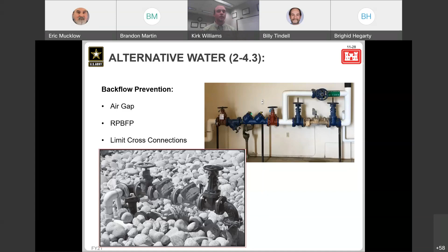This photo is from that AWWA manual, showing where you have a potable source and a non-potable source, and you would physically remove the elbow to make the connection, so there's no cross contamination - they have a cross contamination plan with it, so someone doesn't just open a valve and contaminate your building's water source. There are a lot of good resources out there, but it's a conscious design effort to do some of that.